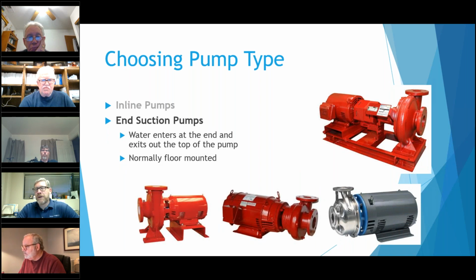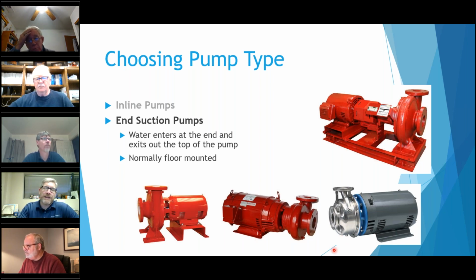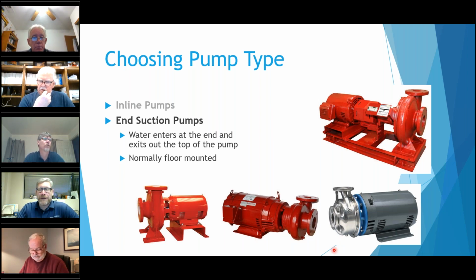Another is an end suction type pump. These are a little bit bigger. The reason they're called end suction is because the water comes in on the end of it and exits out the top. They're generally mounted on the floor. They should be. I've seen where they're mounted in the ceiling. It's not really recommended. You usually get a lot of vibration, but I've seen them mounted on unistrut up in the ceiling, hanging off the pipe somewhere where there's mounting. It becomes very difficult to make sure they're all in line, and also to reduce the vibration these things would have. But generally speaking, they're mounted on the floor.